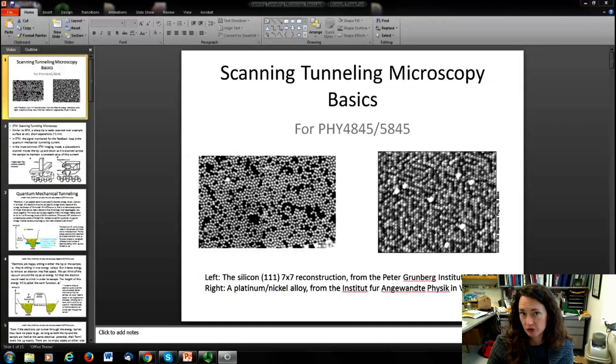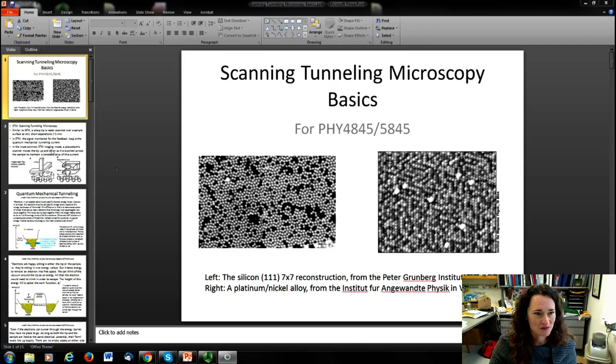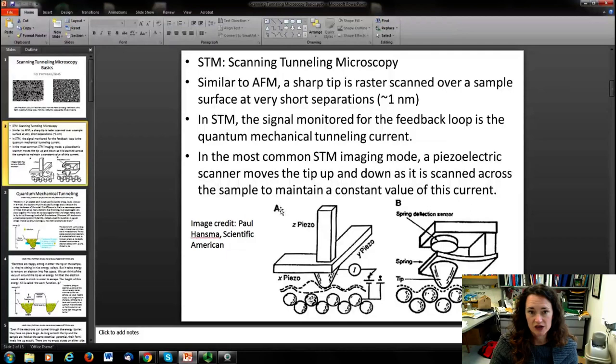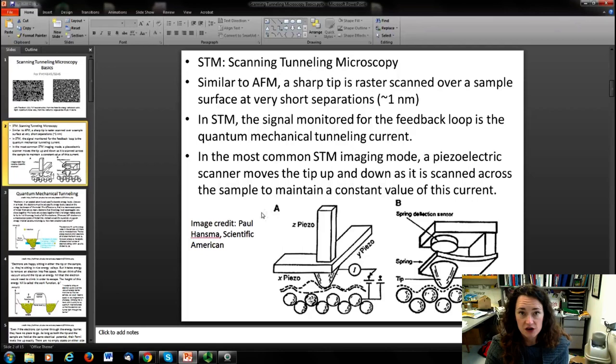As we'll discuss, you can even get sub-atomic resolution sometimes with the STM if you put forth a lot of experimental effort. So how does this technique work? STM, or scanning tunneling microscopy, in many ways is similar to AFM, or atomic force microscopy. You have a sharp probe tip that's raster scanned in a rectangular or square array over a surface at very short tip-sample distances on the order of a nanometer or so.